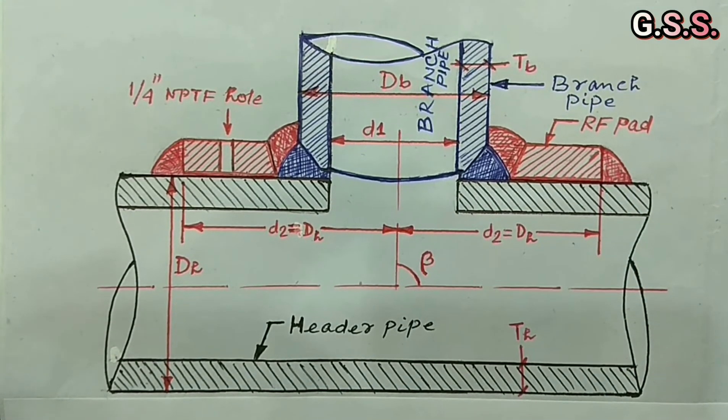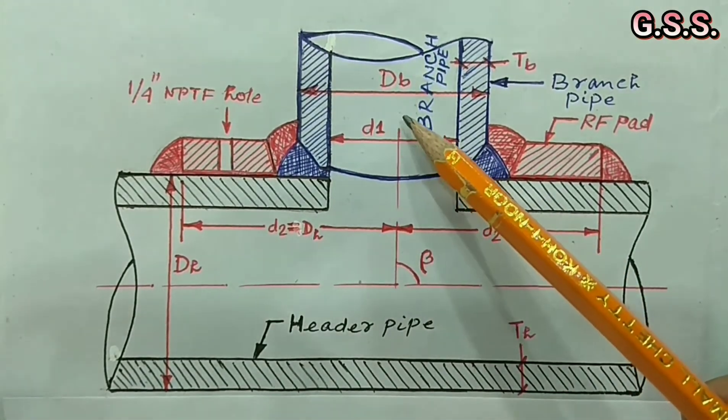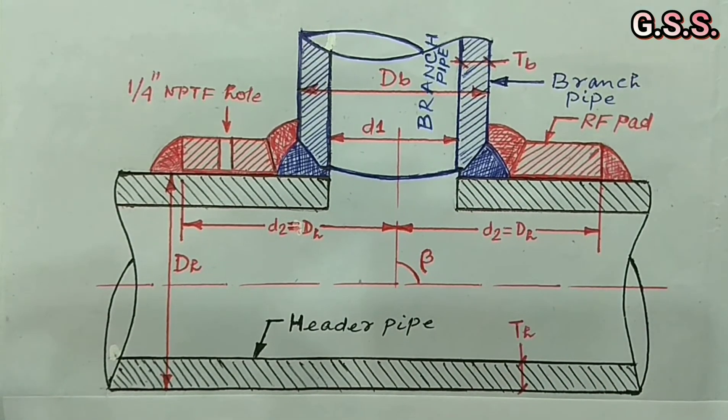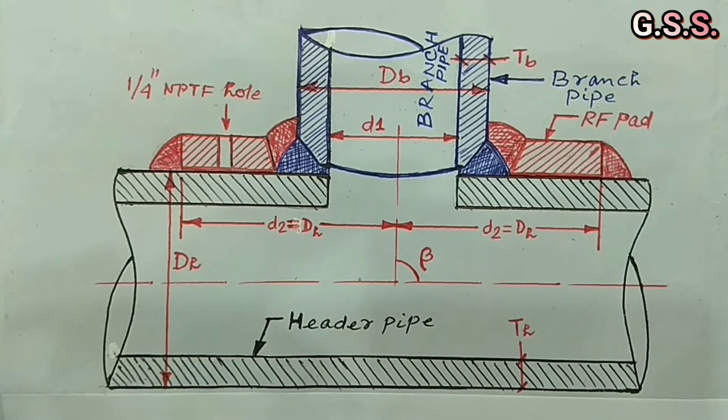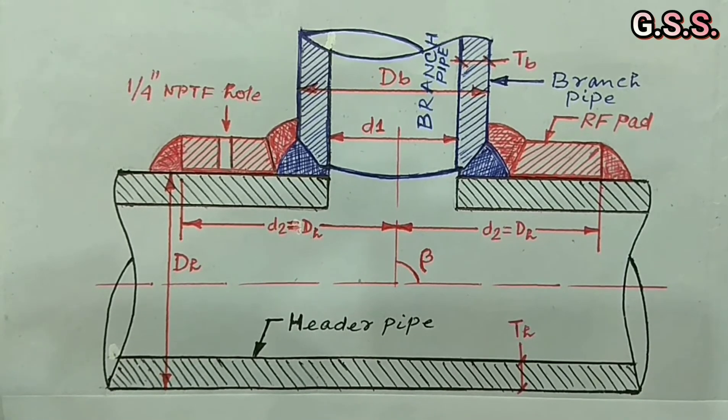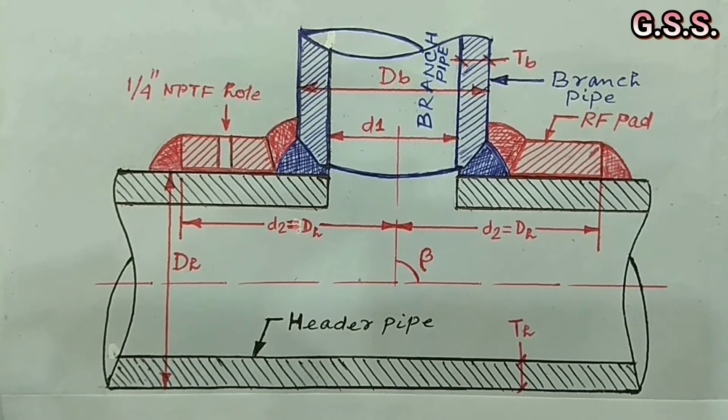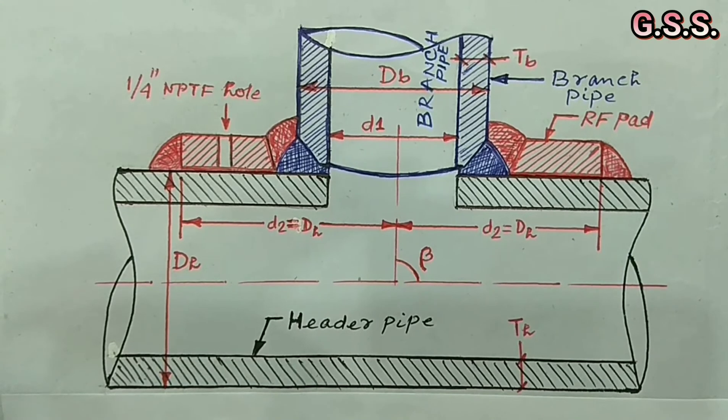Pipe to pipe direct branching is applicable for branch size of 2 inch and above. In case of direct branching, we have to perform two checkpoints. One checkpoint is branch calculation from internal design pressure point of view as per ASME B31.3, and another checkpoint is whether the branch is safe from pipe stress point of view.